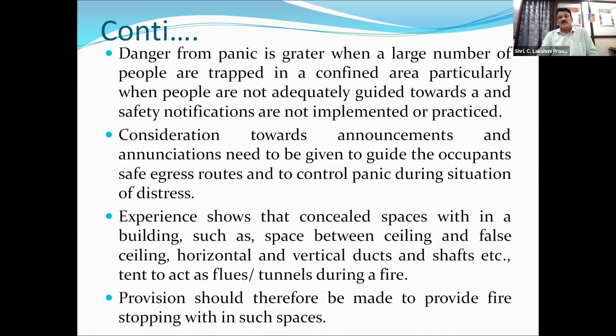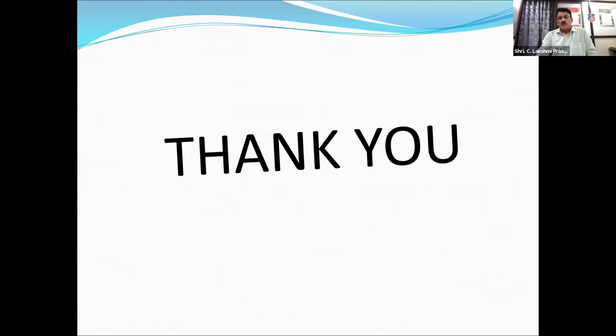Then the concealed spaces also play an important role, and vertical ducts that are punctured in every floor for running various services. If they are not protected properly, they will act as channels for spreading smoke and heat in a fire in the building. Such openings have to be properly protected, and fire stop material has to be provided wherever such openings are made for running various services in the building. So this is the first part. Then we go to Part 4.